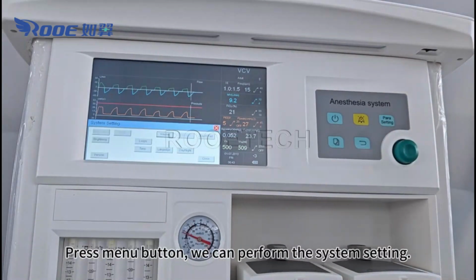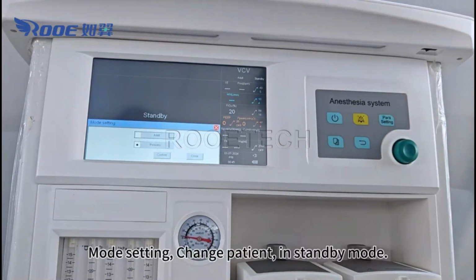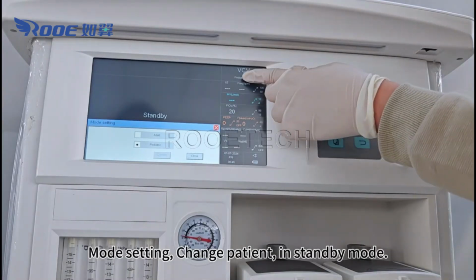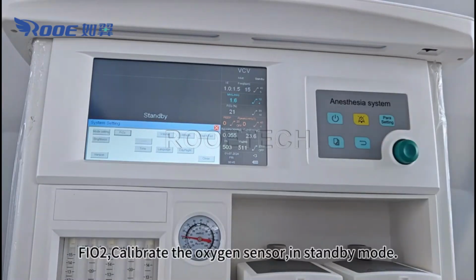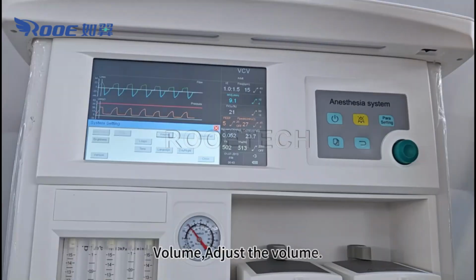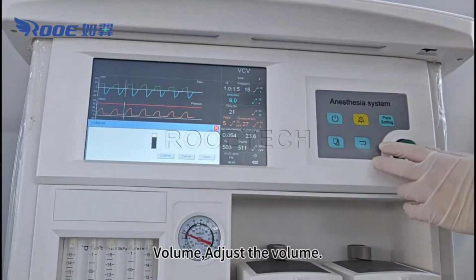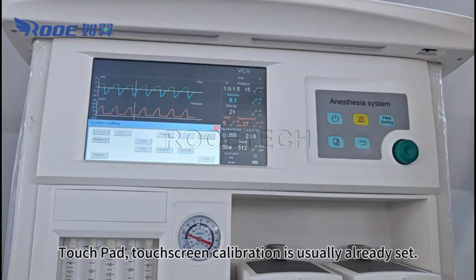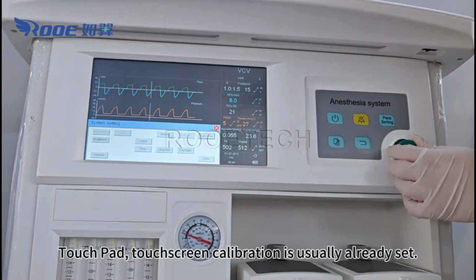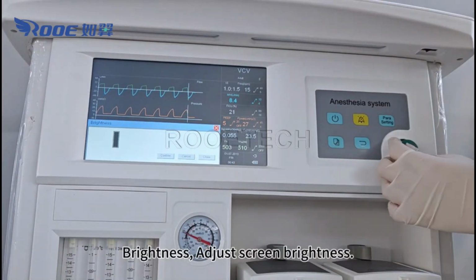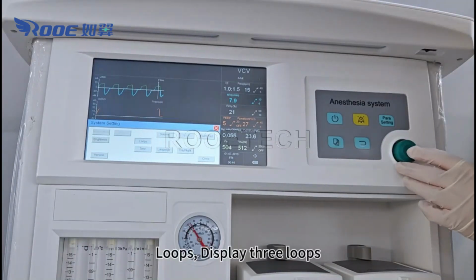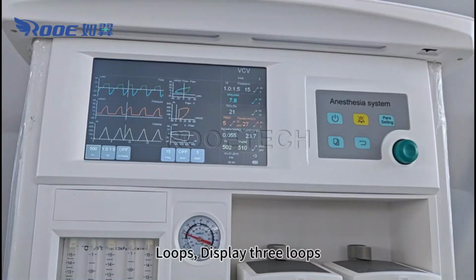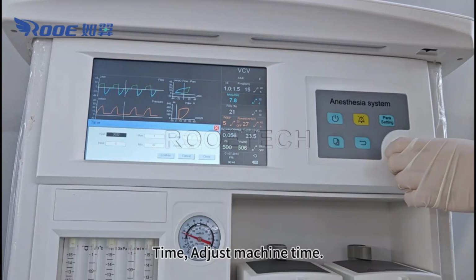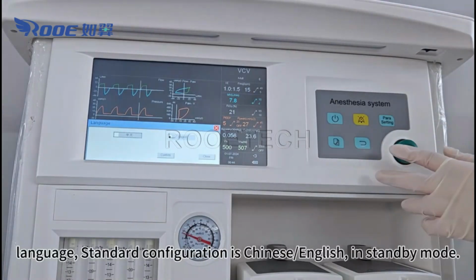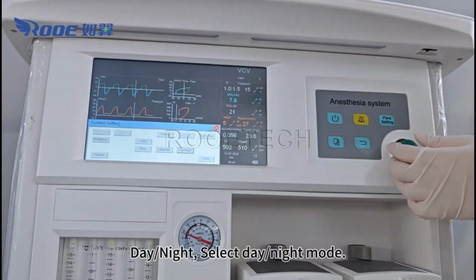Press menu button, we can perform the system setting. Mode setting, change patient in standby mode. FiO2, calibrate the oxygen sensor, in standby mode. Volume, adjust the volume. Touchpad, touchscreen calibration is usually already set. Brightness, adjust screen brightness. Loops, display 3 loops. Time, adjust machine time. Language, standard configuration is Chinese/English, in standby mode. Day/night, select day/night mode.